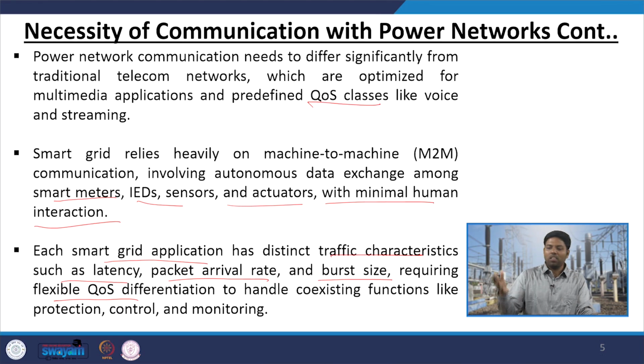For example, in protection, the difference between backup and primary protection has to be more than a certain time limit, and the fault must be cleared within a certain time limit as per standards. So if data about a fault occurring arrives after 5 or 10 seconds, how can you clear the fault within 2 seconds? You cannot.